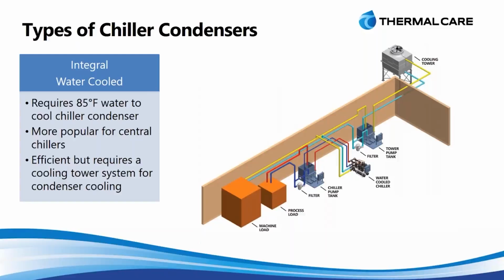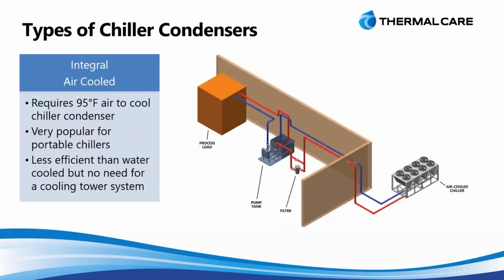It's a very efficient means of doing it, but now you have to consider a whole other infrastructure system of a cooling tower system to support that chiller. So if this type of system already exists in your facility and you just want to add the chiller on, that may be a very viable solution for you. And that's why we would offer a water-cooled unit. If none of that exists, you really don't want to start to build a whole extra infrastructure just to support your chiller infrastructure. So that's where we would start to talk about these next two.